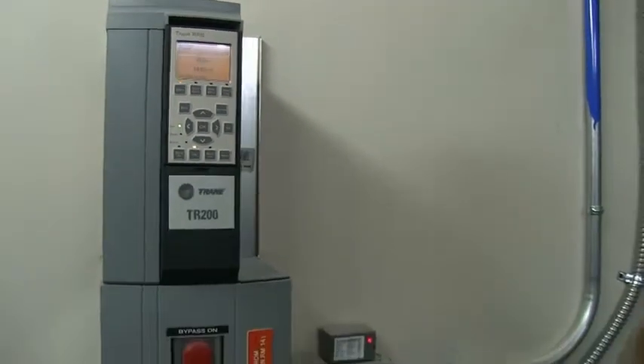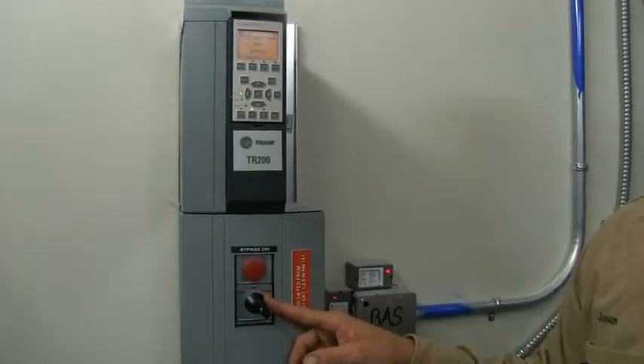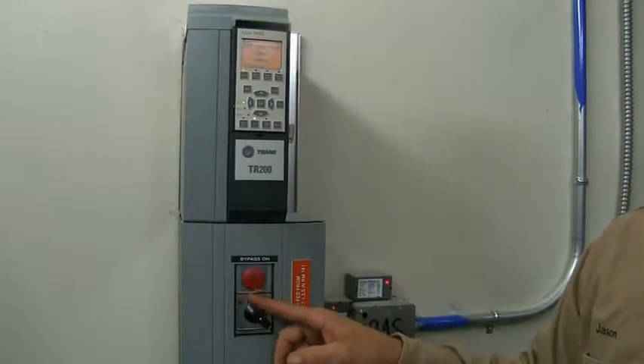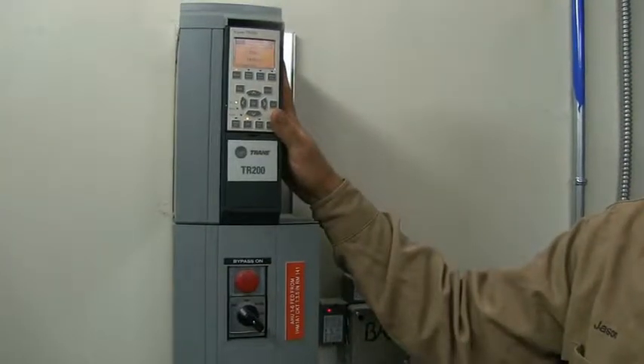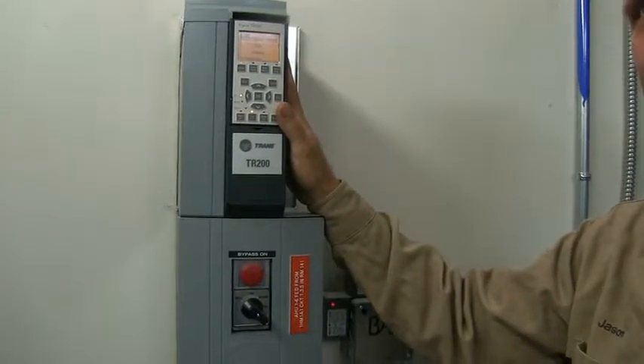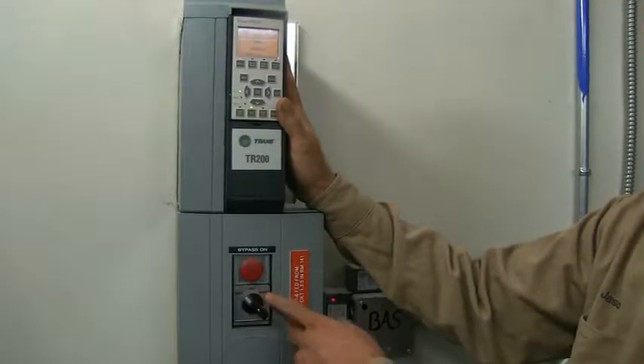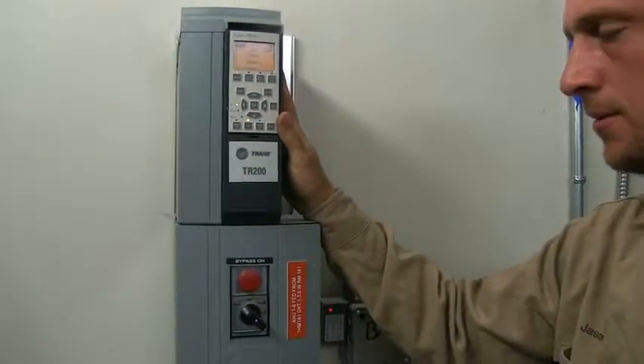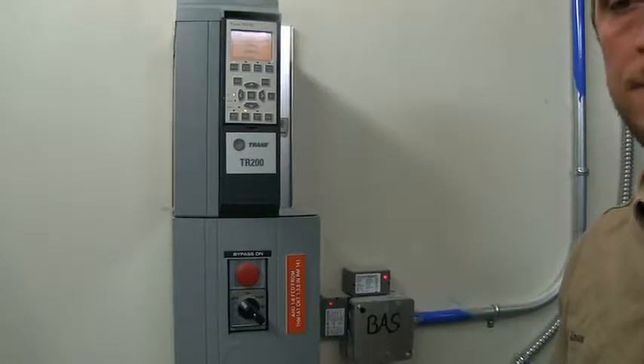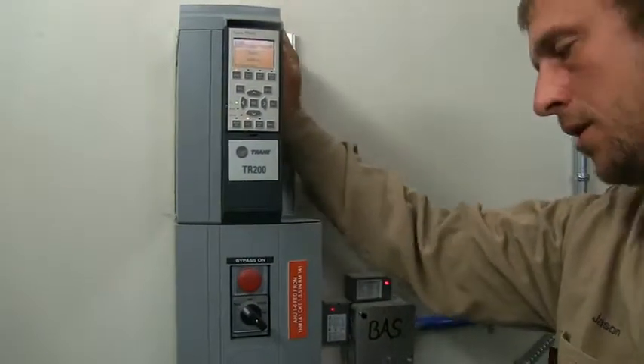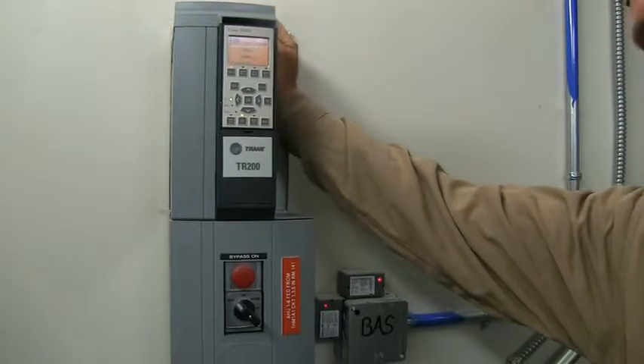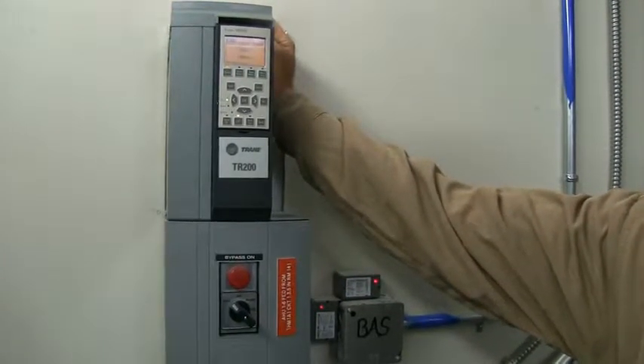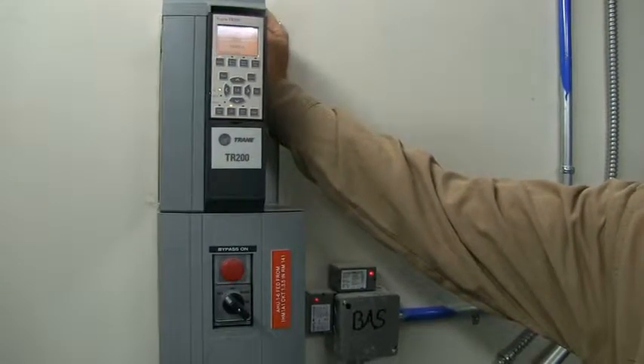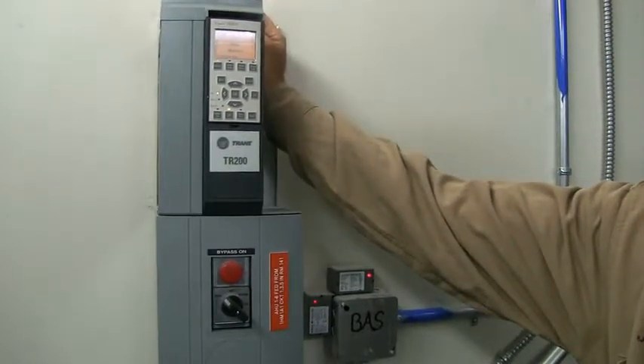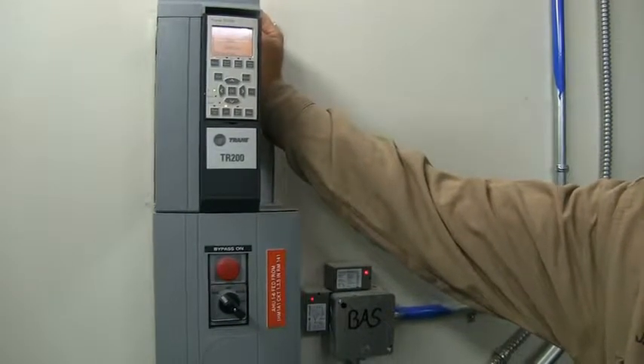Lastly is this toggle button down here to the left that powers the drive so you can run the machine through the VFD. The next setting is off. When you turn that off, it'll remove power from the display, and the last setting is the bypass setting. If for some reason the VFD fails, you can put the drive in bypass, and what that will do is run the fan motor at 100% with no control. There will still be safeties, but we will not be getting a speed signal from the BAS system.